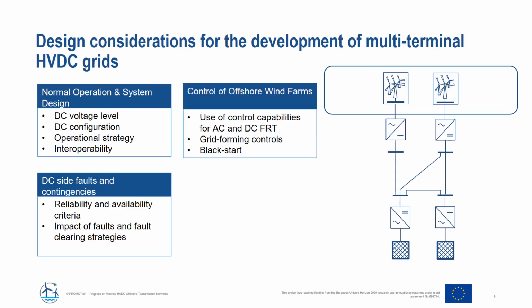For future offshore grids integrating several gigawatts of offshore wind farms, it has to be clear what the role of the offshore wind farms is. So, for example, with regard to their control capabilities for AC and DC fault ride-through, the use of grid forming controls within these offshore wind farms, or the use of them for black start of the overall DC system.